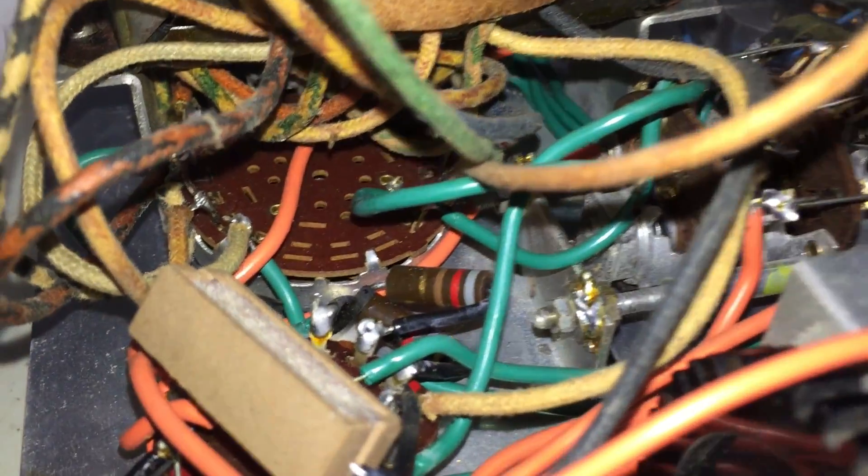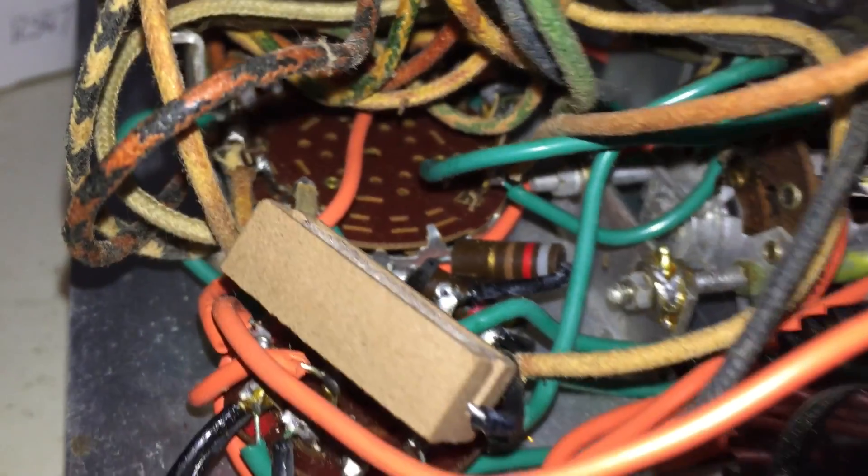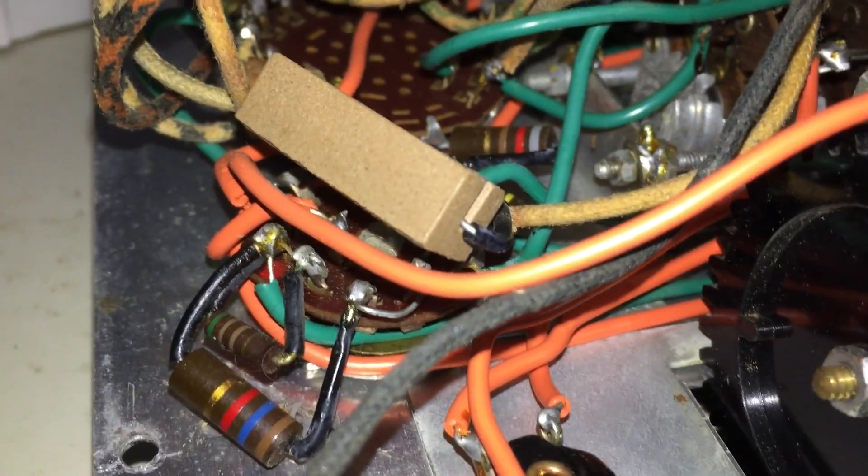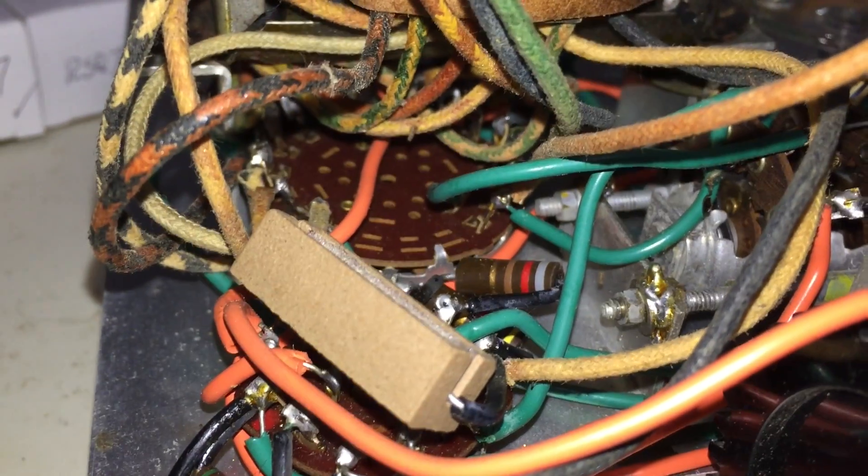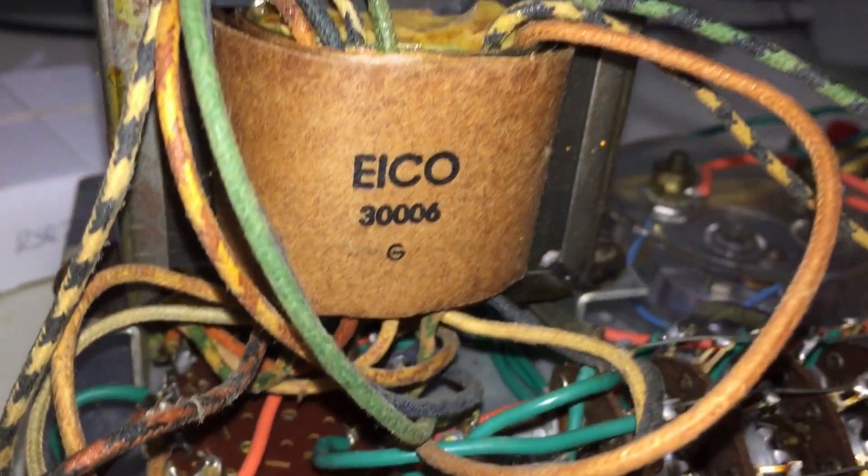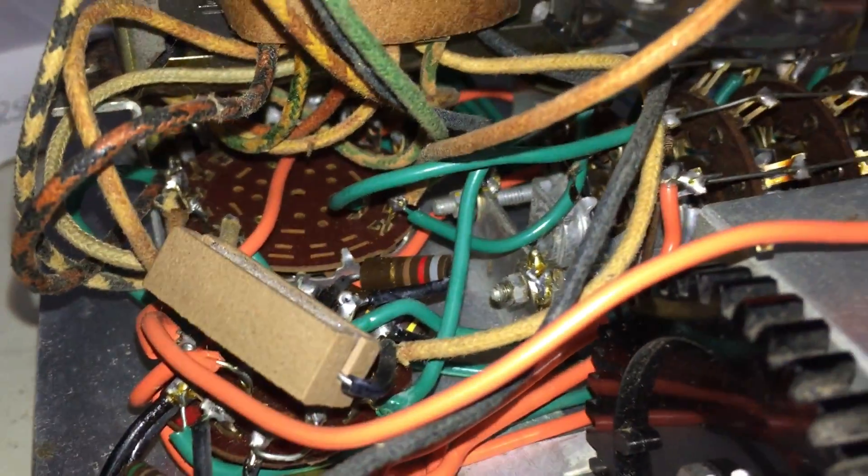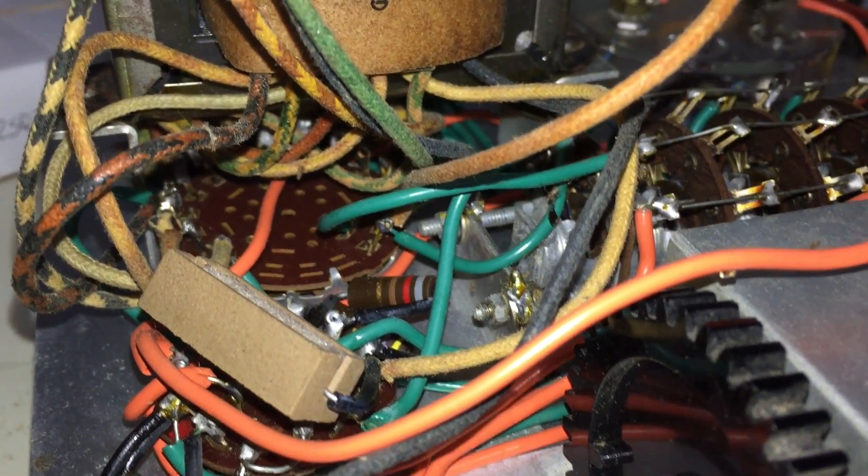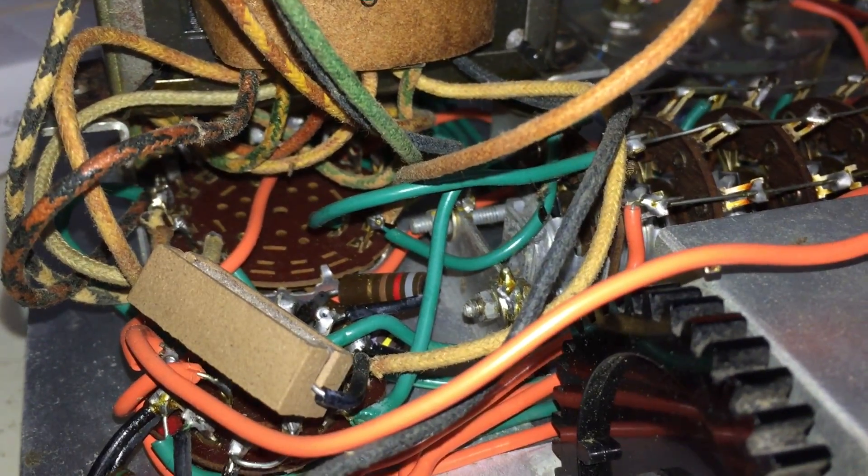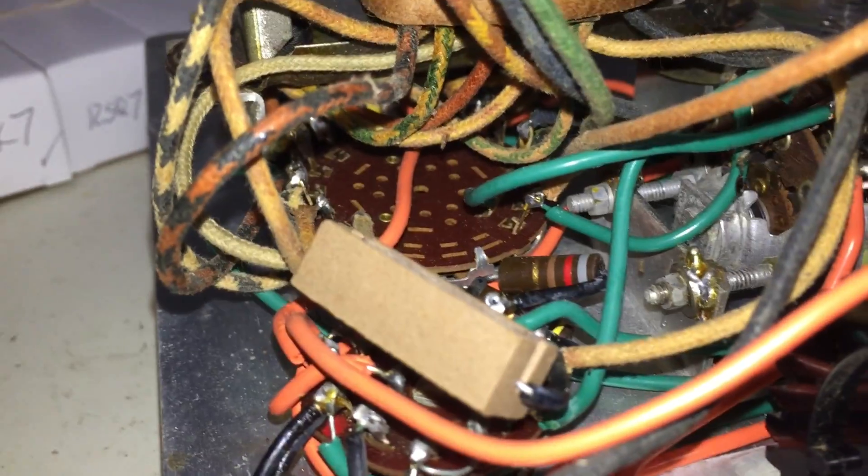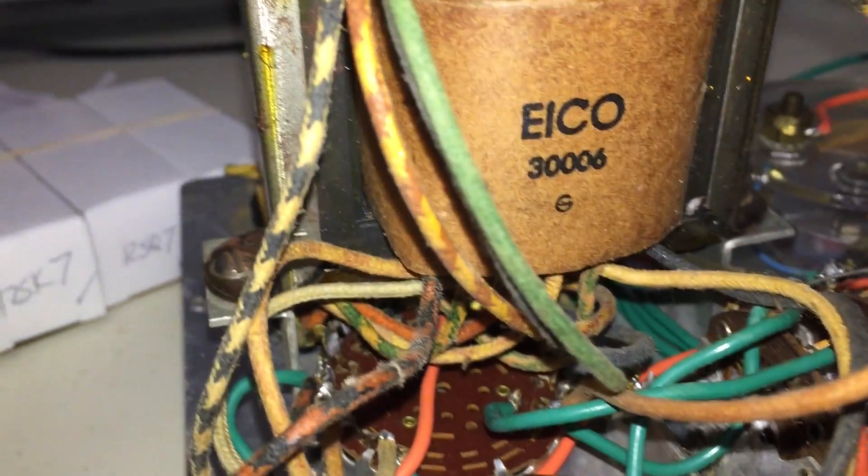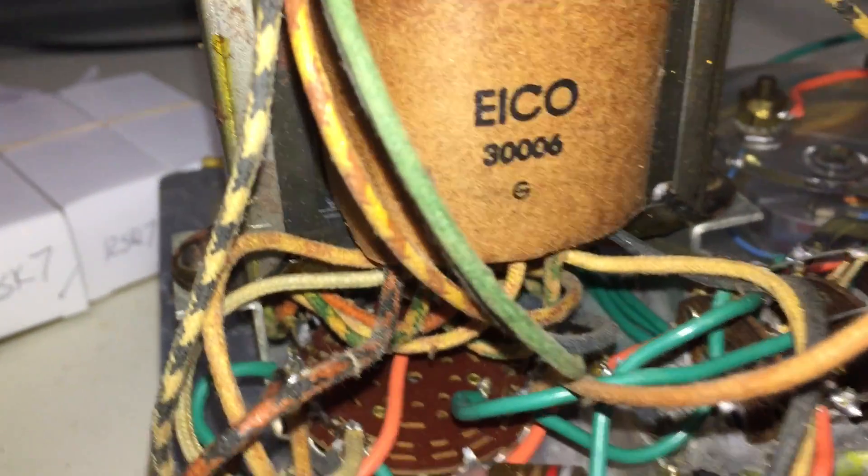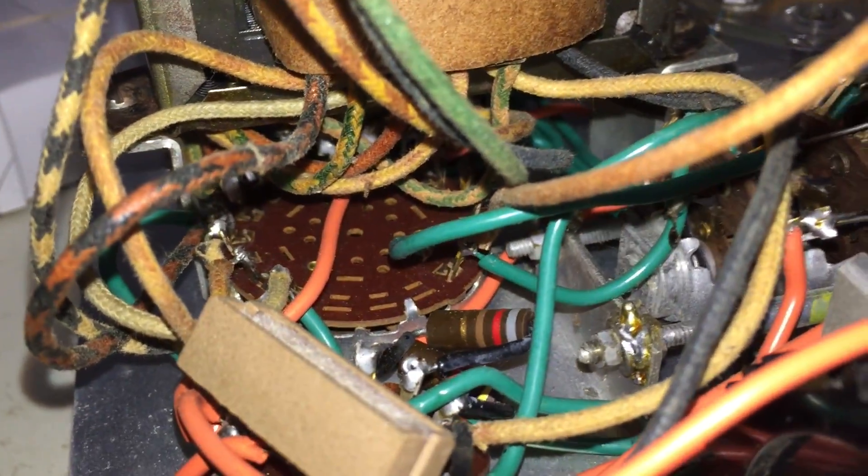Yeah, I'm not seeing that AC coming out the other side here. So I'm gonna have to do some investigation. This is where we're losing it. I know the transformer is good. After the transformer, we're gone. So let me take a look and see what's going on here. I'm gonna have to find one side of that coil and come off the other side of that switch and see if I could fix this.